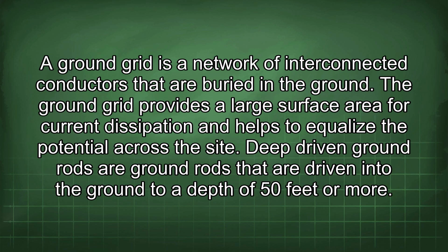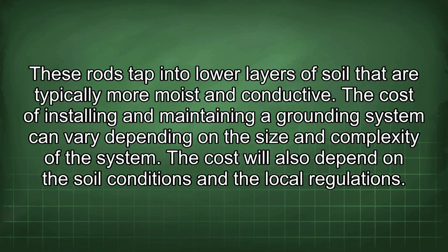A ground grid is a network of interconnected conductors that are buried in the ground. The ground grid provides a large surface area for current dissipation and helps to equalize the potential across the site. Deep-driven ground rods are ground rods that are driven into the ground to a depth of 50 feet or more. These rods tap into lower layers of soil that are typically more moist and conductive.